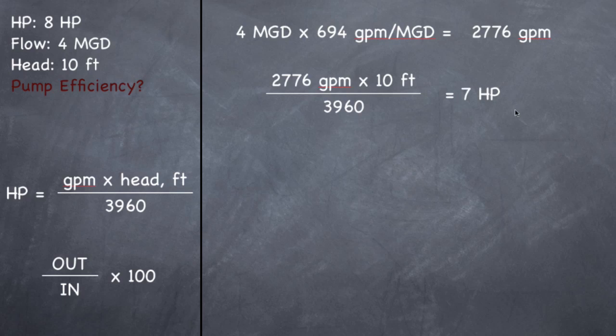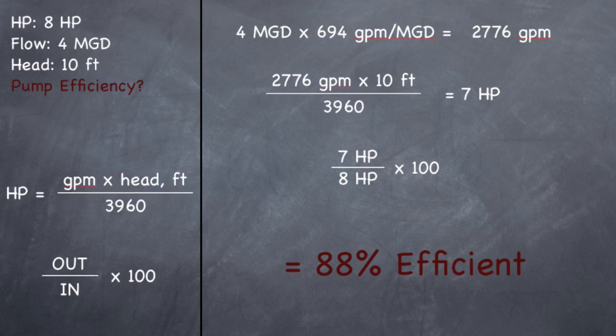In actuality, this pump is operating at 7 horsepower instead of 8 because it's pushing water upward, so you're losing efficiency. Taking 7 horsepower output divided by 8 horsepower input times 100 — this pump is 88% efficient. It's a fairly simple problem, just a new formula you have to memorize. It's not a difficult formula and it shouldn't give you too much trouble.